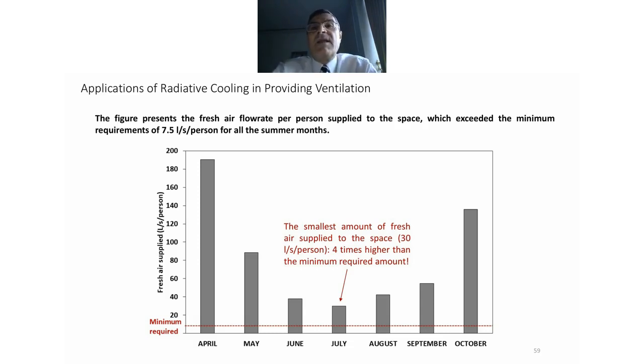So tank 1 was integrated with the PCM. This figure presents the fresh air flow rate per person supplied to the space, which exceeds the minimum requirement of ASHRAE's 15 CFM or 7.5 liters per second per person. Okay, in the summer months it was maintained constant throughout the day, and the entire ventilation load was met by the proposed passive system. So we could meet what ASHRAE said and a lot more than that.